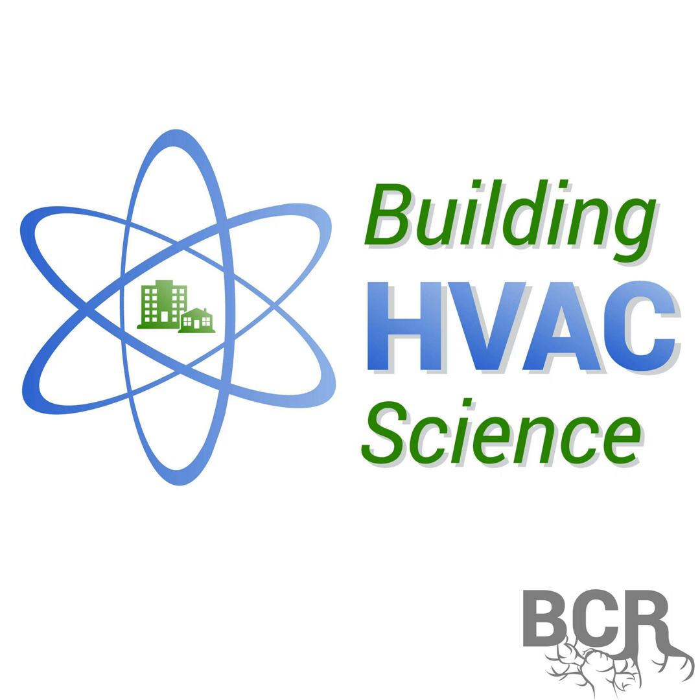And then similar to other HRVs or ERVs, we'd have two ducts going to the outside, a fresh air supply and an exhaust, and then two branches that are supplying and returning to the house. We run at higher airflow rates than what most people are used to as far as fresh air ventilation. So we'll operate at around 200 CFM, where the ASHRAE residential ventilation standard 62.2 would typically specify somewhere in the range of, say, 40 to 80 CFM for a typical size house with maybe 2, 3, or 4 bedrooms.